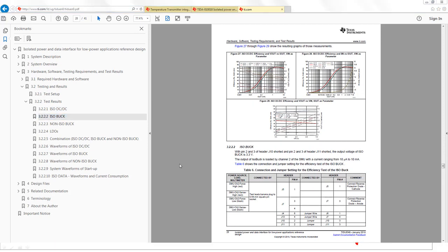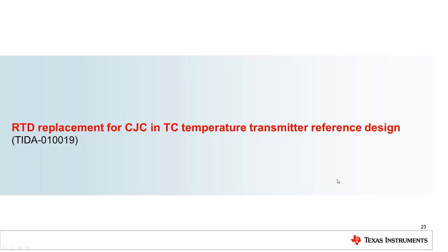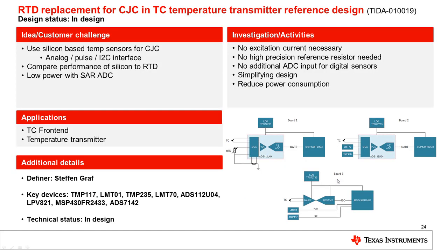Let's have a closer look into this specific reference design — RTD replacement for cold junction compensation in thermocouple temperature transmitters. In this reference design, we investigate the performance of a PT100 element versus a silicon-based temperature sensor. By using such a temperature sensor, no excitation current is required. Also, no high-precision reference resistor is needed. In case you are using a temperature sensor with a digital output, no additional ADC input is needed either.